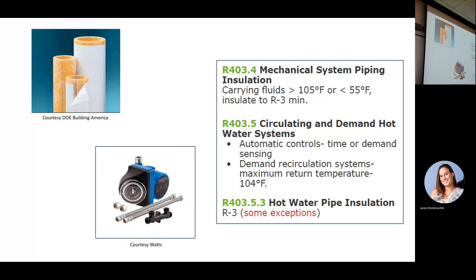And so we have some requirements in here that if the temperature of the fluid or whatever's in the line, and by the way, gases and liquids are considered fluids, if we're not in this range, we need to insulate to R3. So our refrigerant lines, the small little copper line is typically in this range, and so we don't insulate it. But the suction line, the bigger line, is cooler than this range, and so we do insulate it. Now, why do we want to insulate cooler lines? So they don't condensate and drip and give us mold problems. And of course, we want to insulate hotter lines because if we're doing a radiant floor system and we have all that piping in the mechanical area, we really need to insulate the distribution piping that's getting it there, and just radiate the heat off the tubing that's in the floor or at a radiator or whatever we're at. And so that's even a smaller amount of insulation, but that's effective.